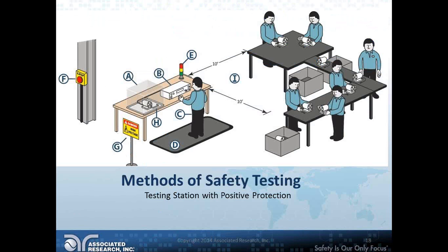So what we have here is a test operator working with the high pot equipment, and the DUT, or device under test, and the test leads from the high pot tester are all enclosed in that enclosure. This is positive protection, and what we've done here is build the door of that enclosure into our interlock. That means we have a magnetic switch on the door. So if that door opens while the test is running, the interlock is broken and the high pot tester immediately stops outputting voltage. Basically you can't run that test if that door is open. That's what we call positive protection.